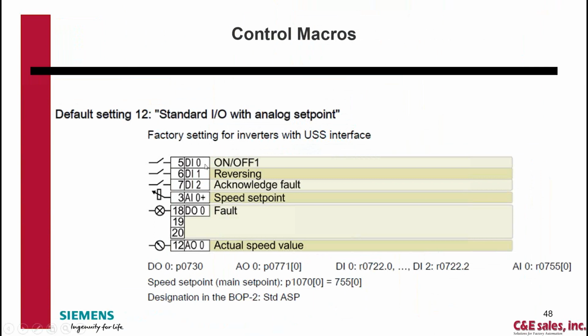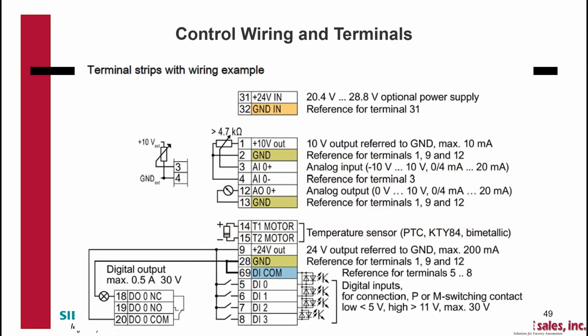Here on off is digital input 0, reverse is digital input 1, fault acknowledge is digital input 2, so very much like the V20 setup was. We do have analog input 0 as our speed set point. So that's what's going to be there. And then this is kind of the terminal layout of the drive as well, and where the wires are needing to land for that. I'll highlight this jumper between terminal 28 to 69. A lot of people forget to include that, so don't forget that jumper.